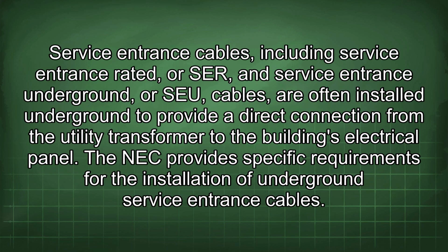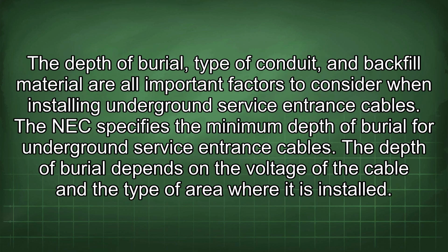Service entrance cables, including service entrance rated, or SER, and service entrance underground, or SEU, cables, are often installed underground to provide a direct connection from the utility transformer to the building's electrical panel. The NEC provides specific requirements for the installation of underground service entrance cables. The depth of burial, type of conduit, and backfill material are all important factors to consider when installing underground service entrance cables. The NEC specifies the minimum depth of burial for underground service entrance cables.